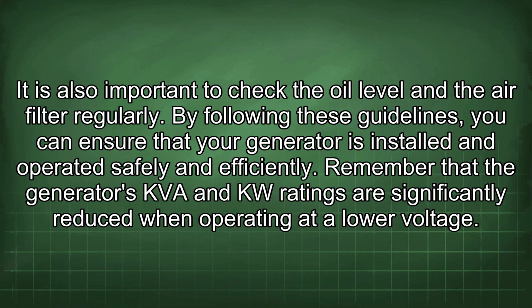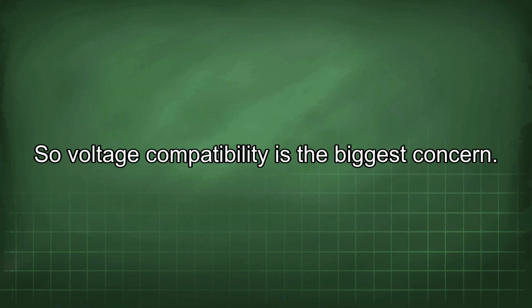Remember that the generator's KVA and KW ratings are significantly reduced when operating at a low voltage. So voltage compatibility is the biggest concern.